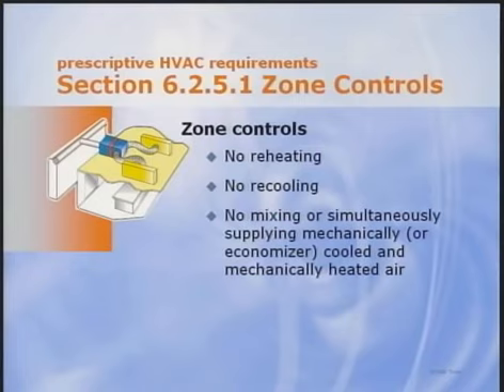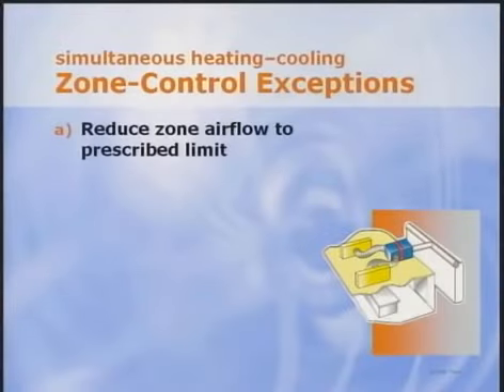There are limits on simultaneous heating and cooling. This includes not mixing air streams, even if the cool airstream has been made that way through the use of an economizer. Note that reheating or recooling, for instance in a desiccant system, is not banned since there are exceptions based on zone airflow. Let's look at those exceptions. First, prior to using new energy for reheat, reduce the amount of zone airflow that must be reheated. There are 5 possible limits that we'll look at in a minute.